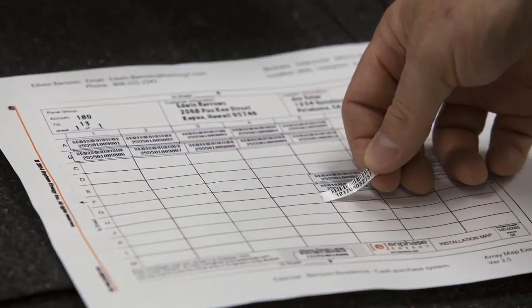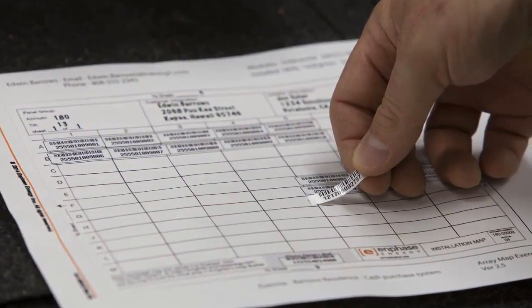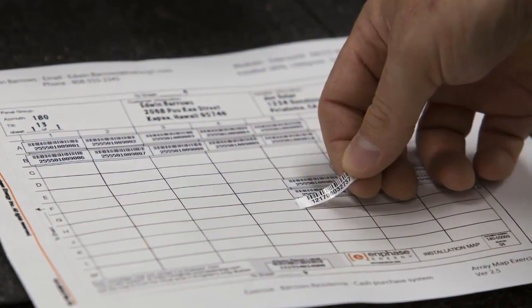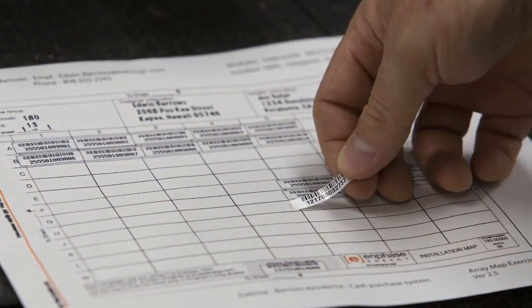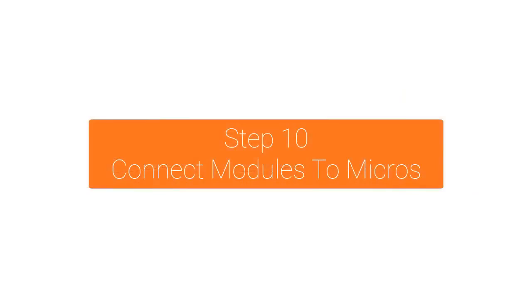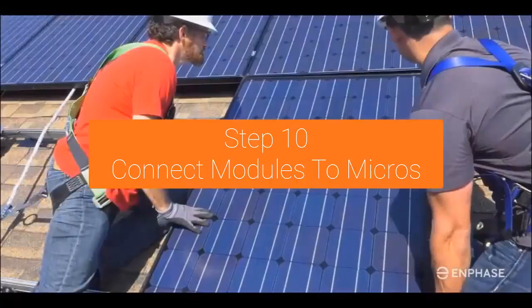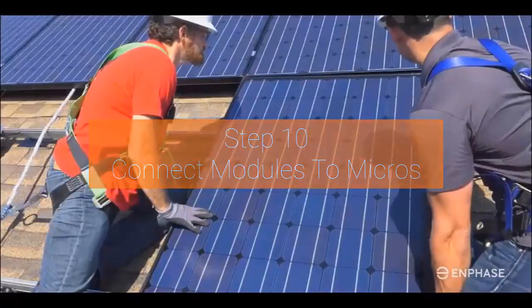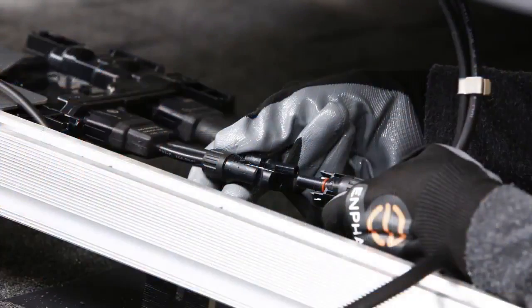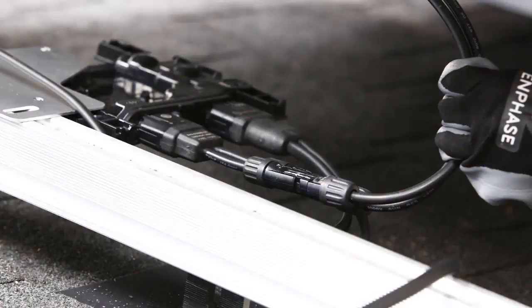Peel the removable serial number label from each microinverter and affix it to its respective location on the paper copy of the installation map. Mount the PV modules above the microinverters. Connect the DC leads of each PV module to the DC input connectors of their corresponding microinverter. Listen for the clicks to ensure they are connected.